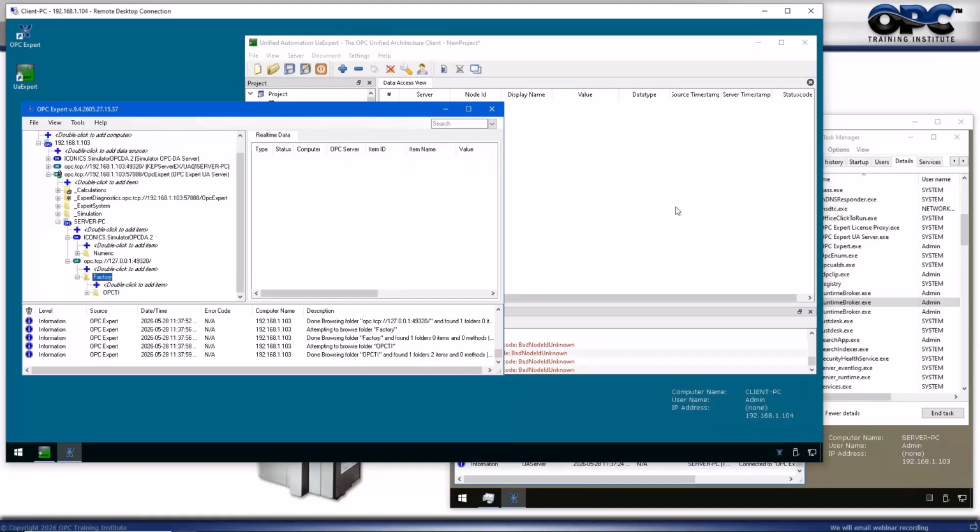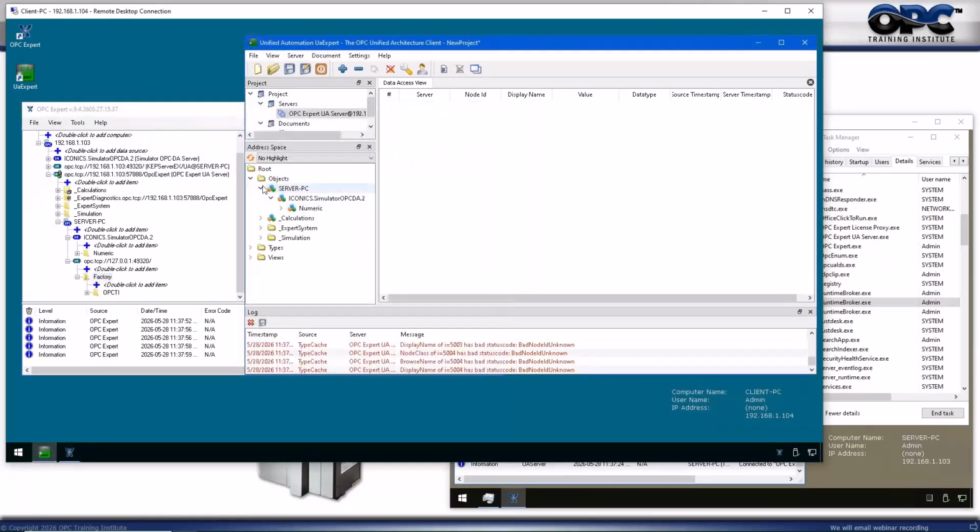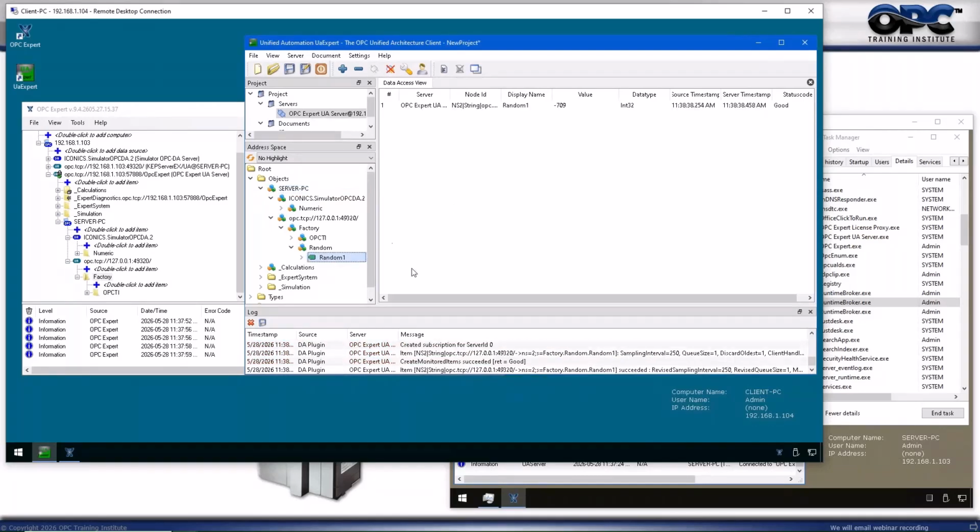But when I go here, watch this. So iconics, I have numeric and I have everything. And, oh, I need to rebrowse. There we go. So iconics, I have numeric and everything. And over here with Kepware, factory, I've got OPCTI and I've got random as well. And you see, only that one item. Only that one item is available. Why? Because that's what I gave access to.